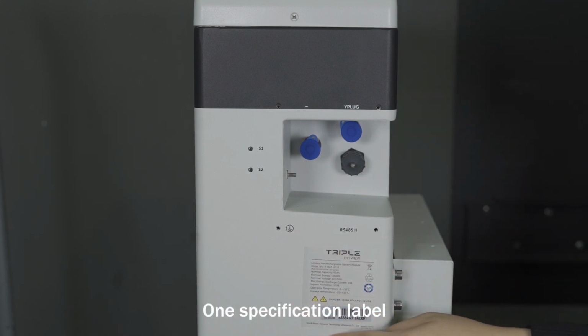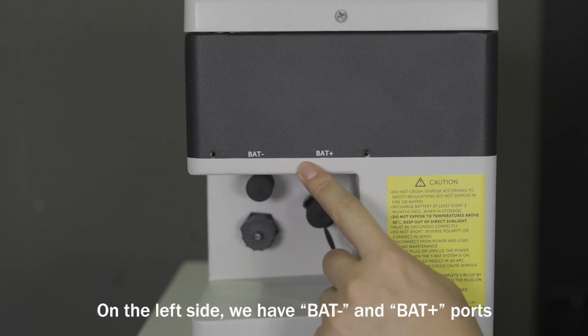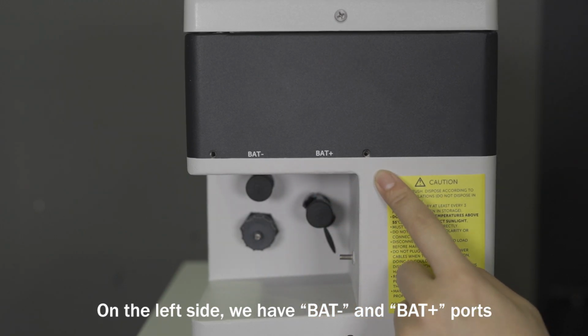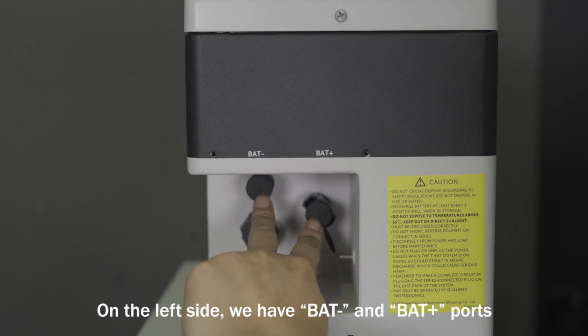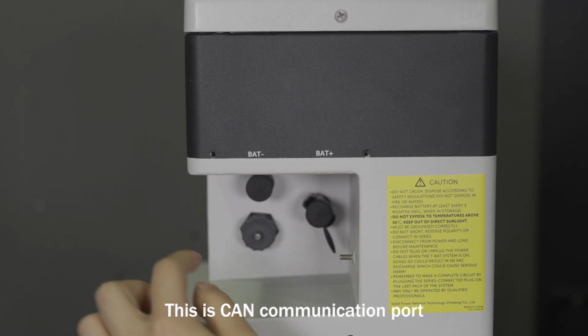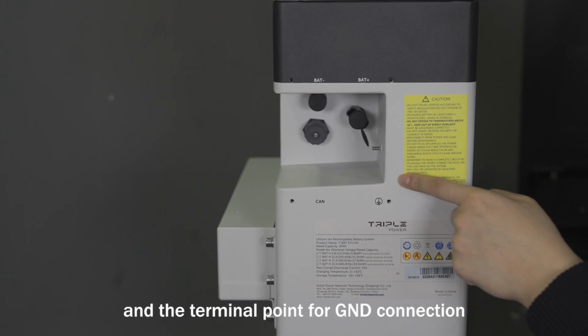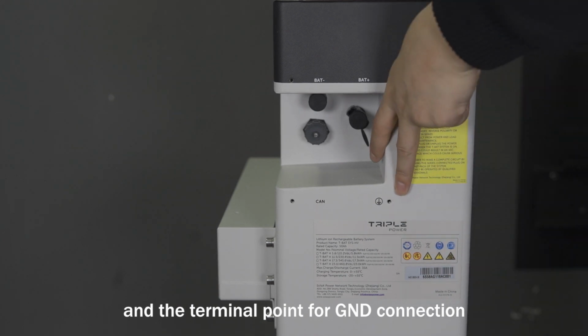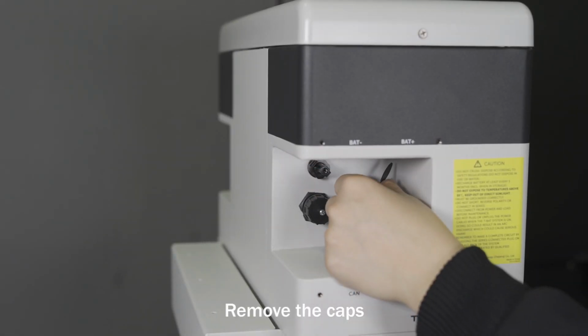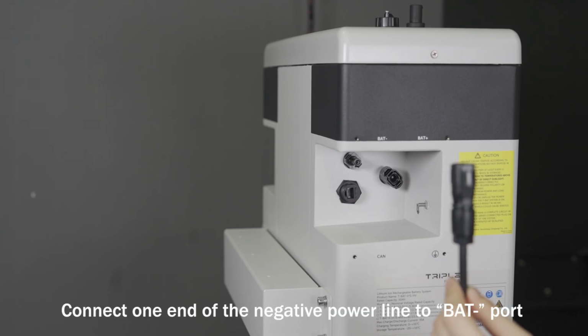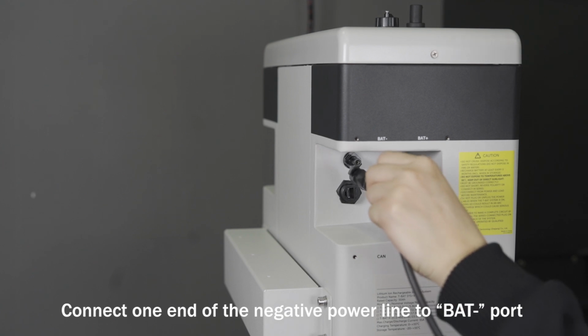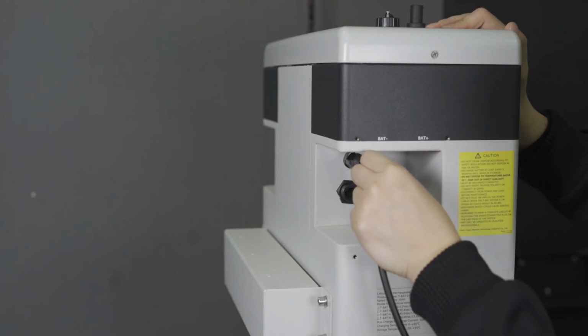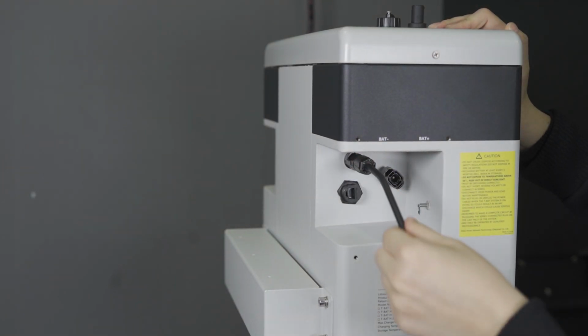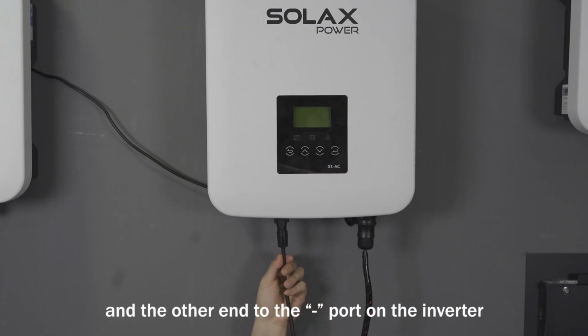One specification label. On the left side, we have BAT negative and BAT positive ports. This is CAN communication port and the terminal point for ground connection. Remove the caps. Connect one end of the negative power line to BAT negative port. And the other end to the negative port on the inverter.